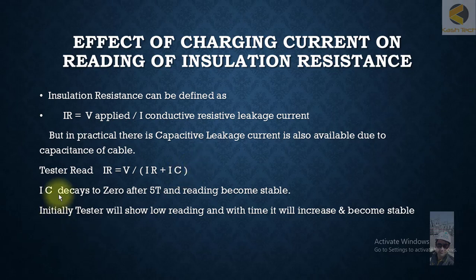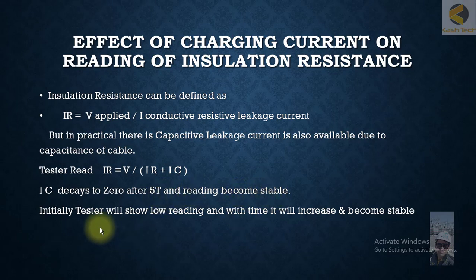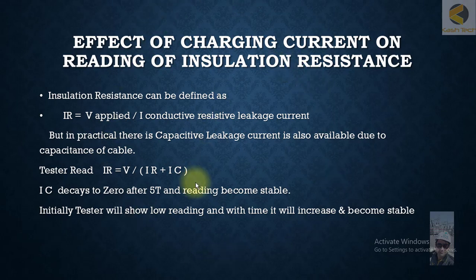The good thing is, if you want to get the correct reading, the IC — the charging current — will decay to zero within five time constants and the reading becomes stable. Initially the tester will show a low reading, and with time it will increase and become stable. So you just have to wait for the right time. For longer cables, the issue is more significant.